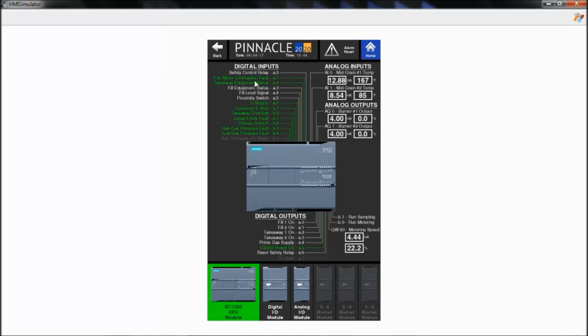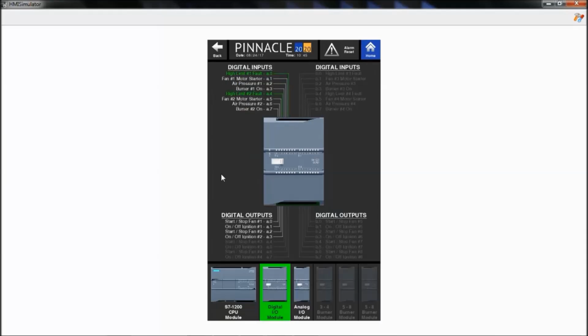On this page, there are a couple of different color codes. White text indicates something installed on the machine that doesn't currently have a signal coming back. Green text means it's installed and you currently have a 24-volt signal coming back. Grayed out text means that component isn't applicable to your machine and you don't need to worry about it for troubleshooting. We can see our digital inputs and outputs as well as any analog signals, and as we go to the next module, we can see all components installed on this machine and the extra pieces that could be plugged in but aren't needed for your current machine.